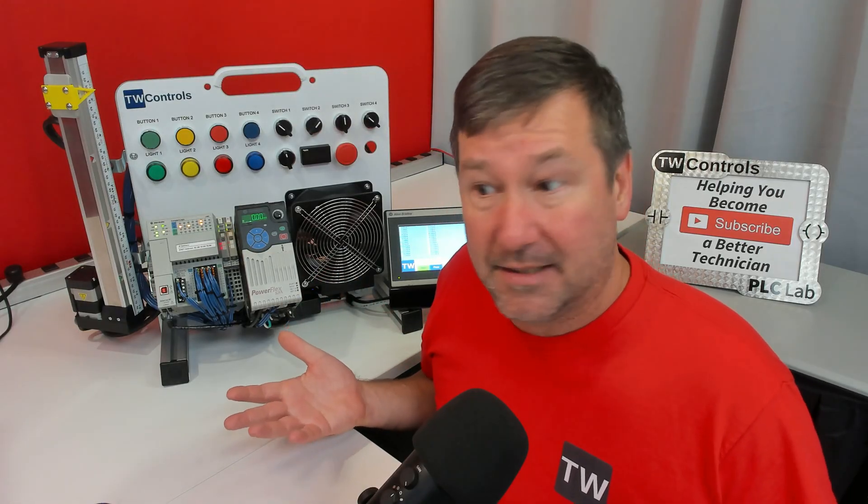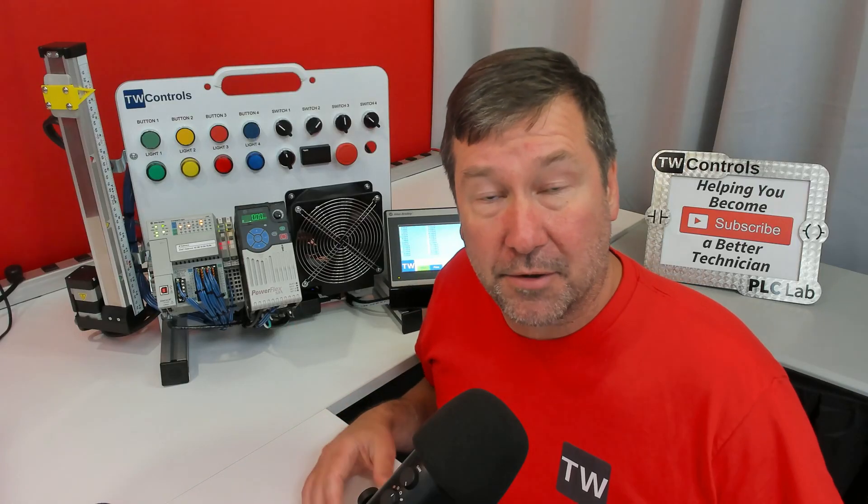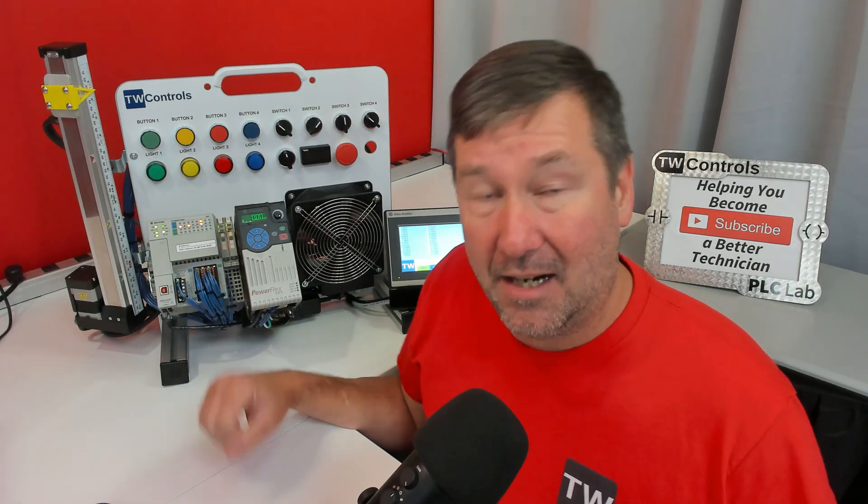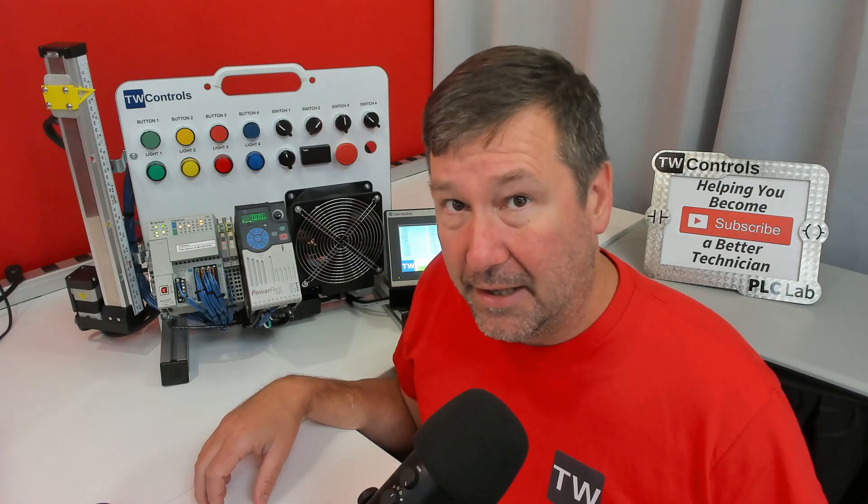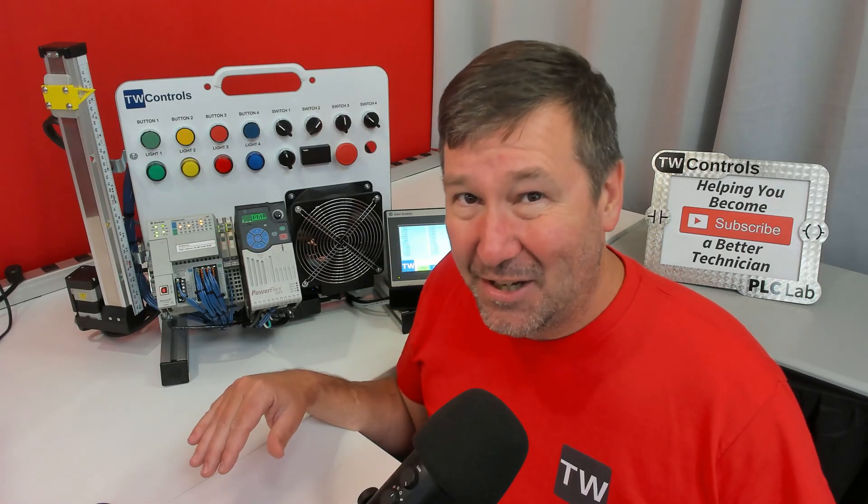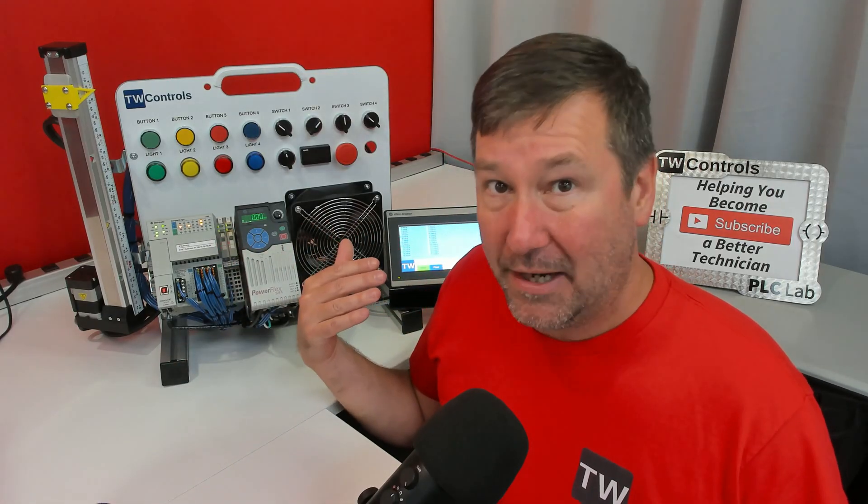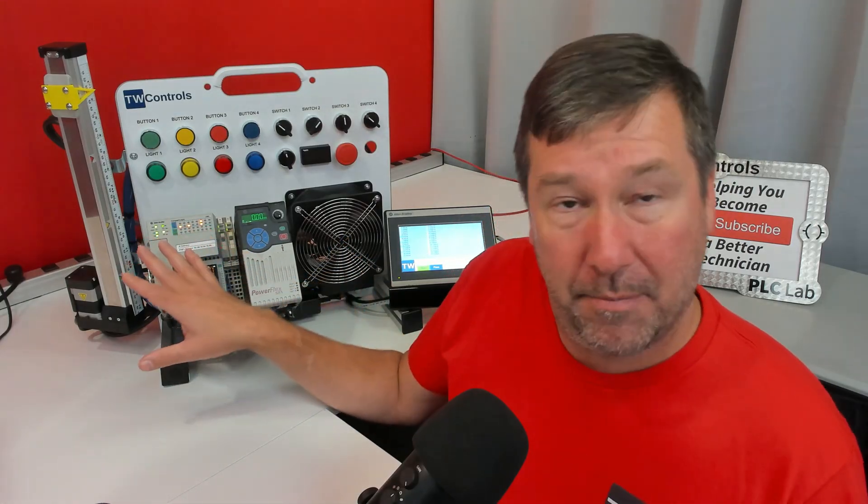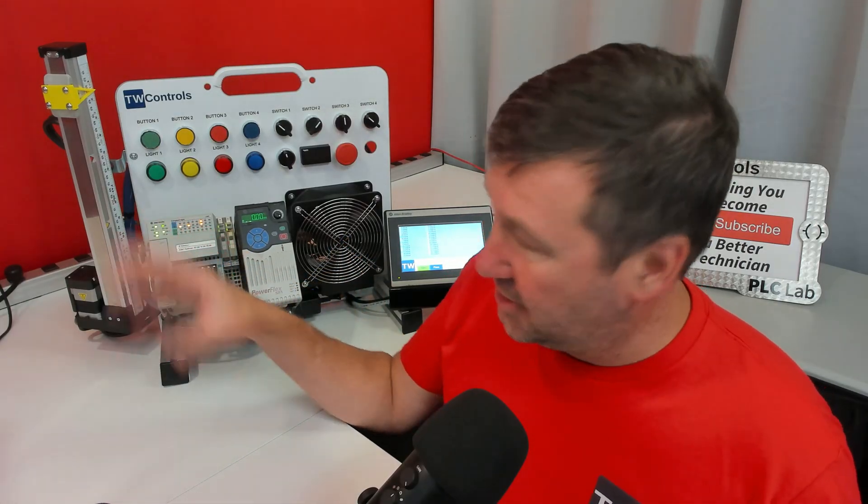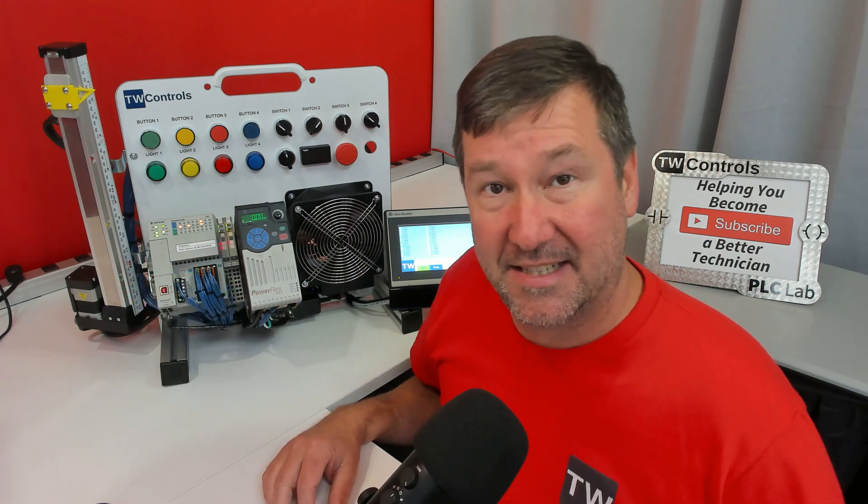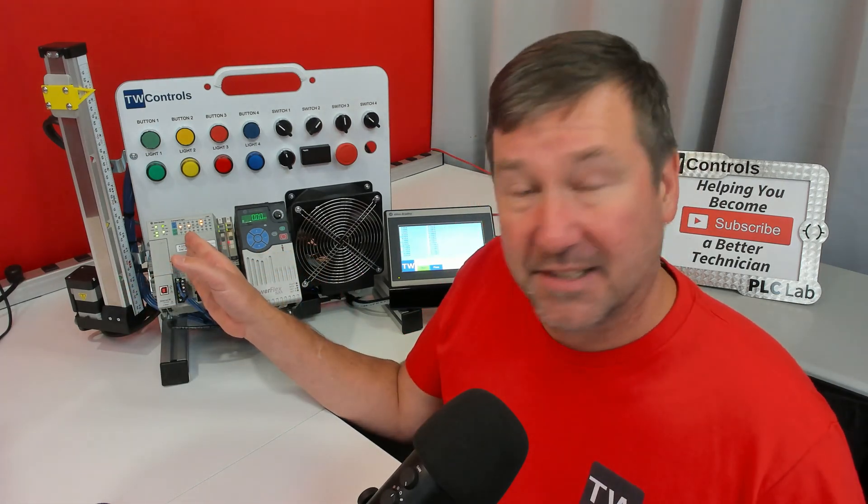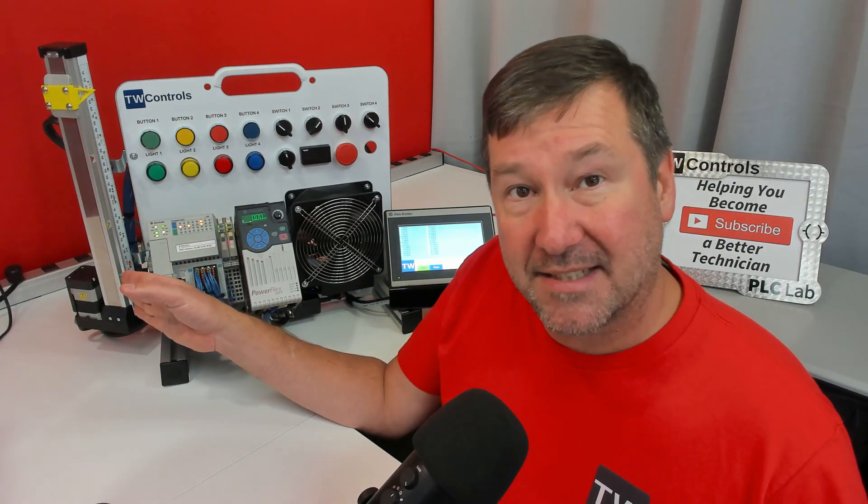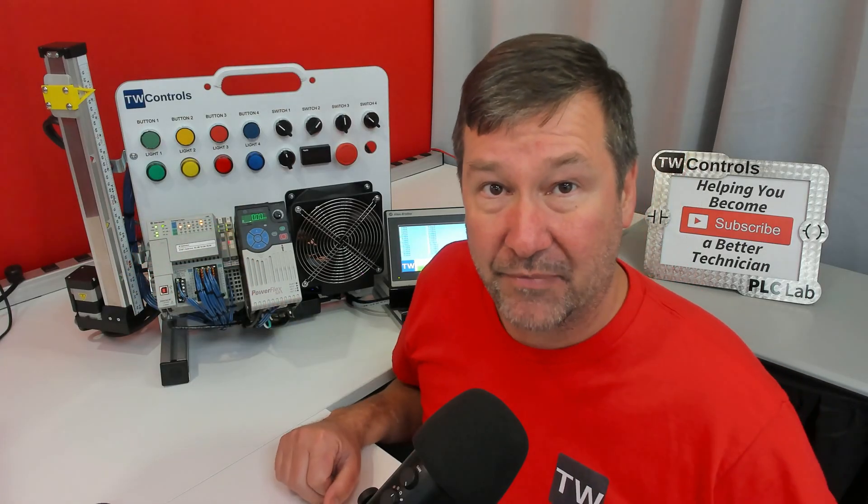Another reason is to minimize our downtime during a failure. We can have the SD card already set up with the program on it, but have it set to not load unless it has a blank program. You have a PLC failure. Your technician swaps the PLC out, swaps the SD card out, powers it up. It'll look and say, hey, I have no program. And it would go to the SD card, read it, and install it.